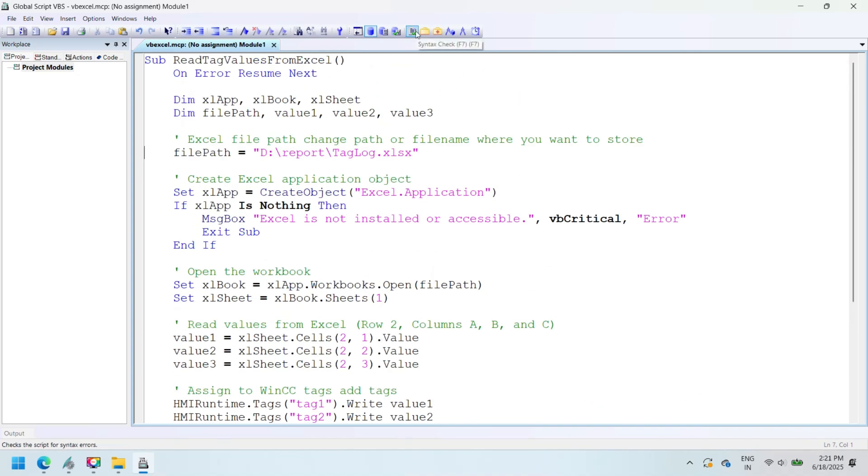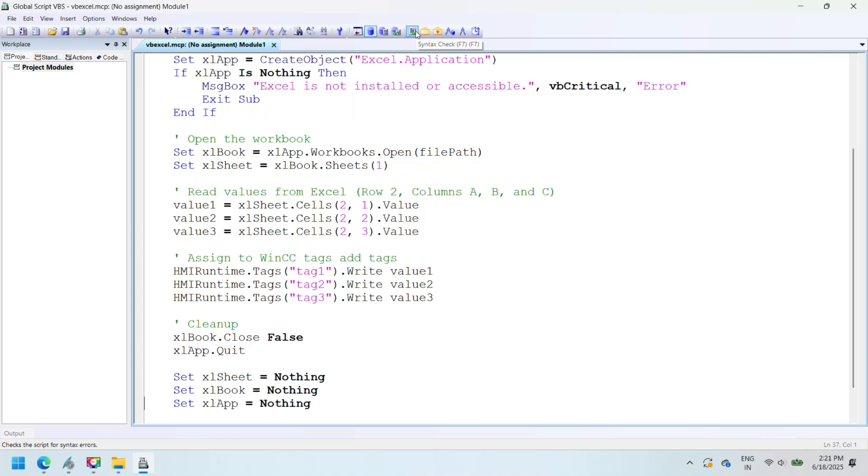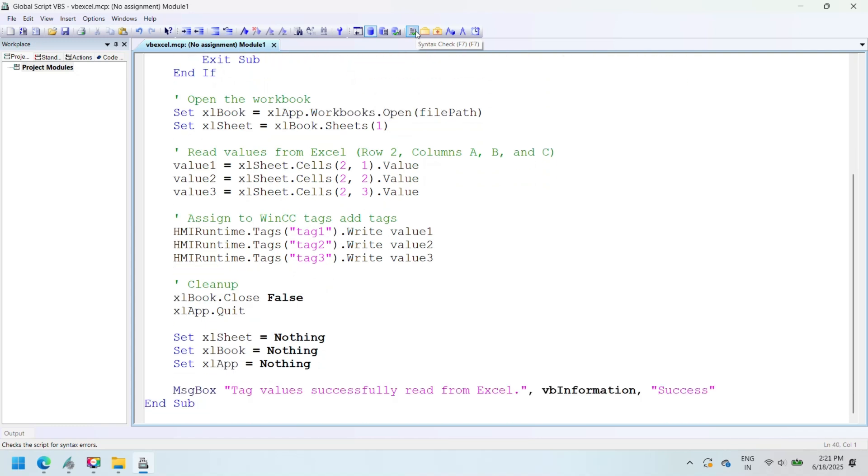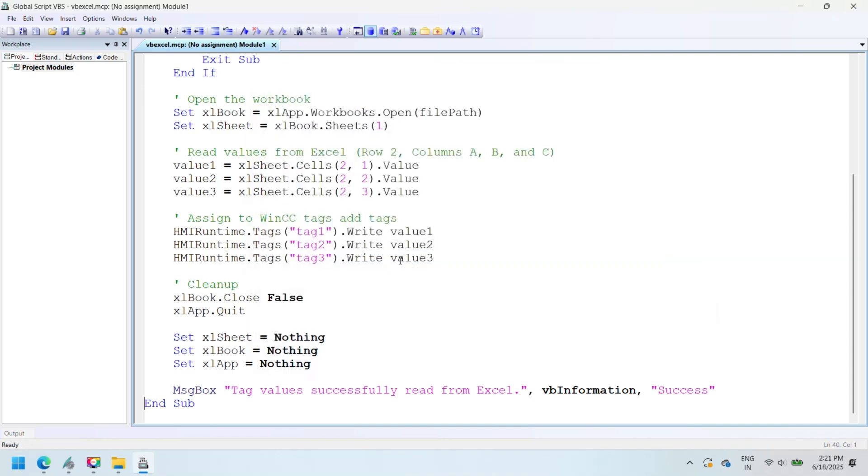After adding the script, perform a syntax check to ensure there are no errors, and then bind the script to the Read button on your SCADA screen. This setup allows operators to import previously logged or manually entered Excel data directly into the SCADA Runtime environment.